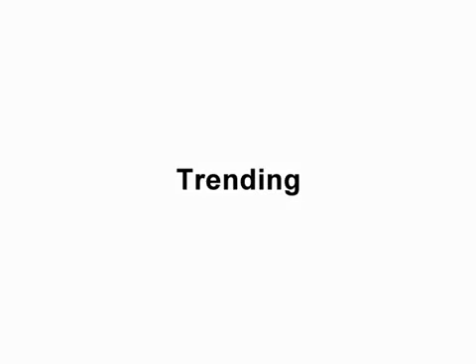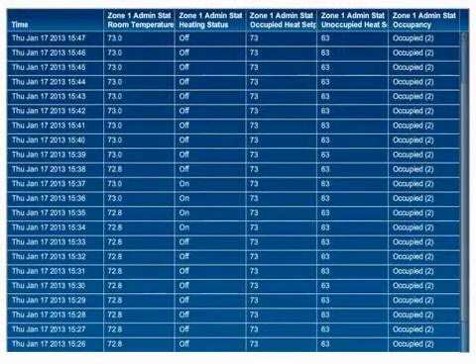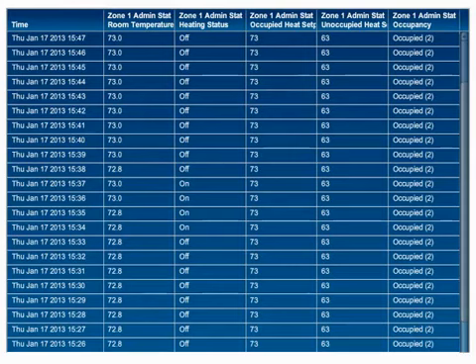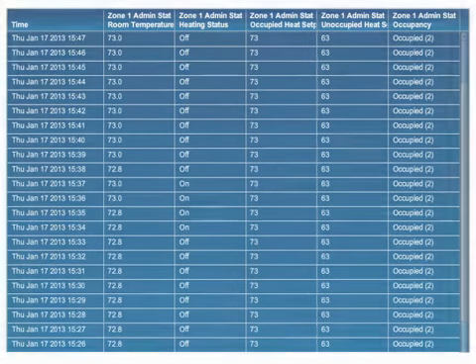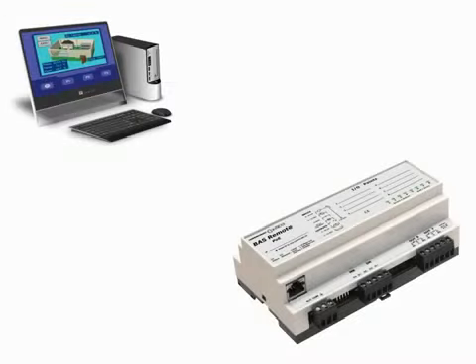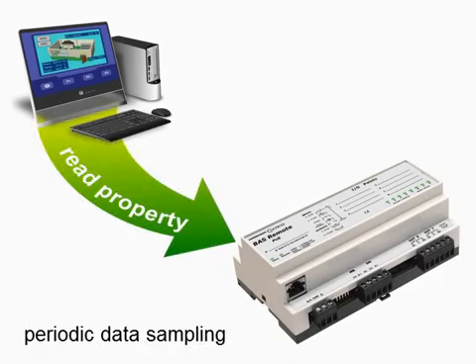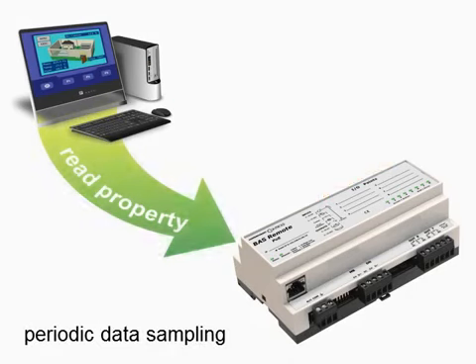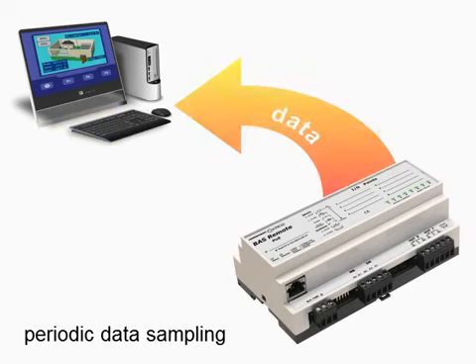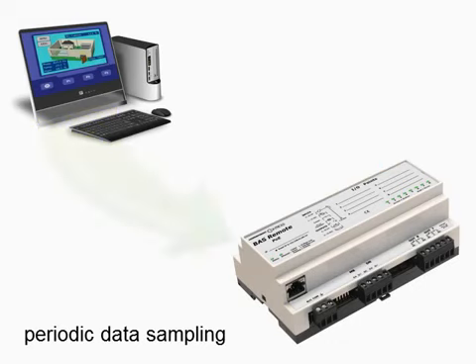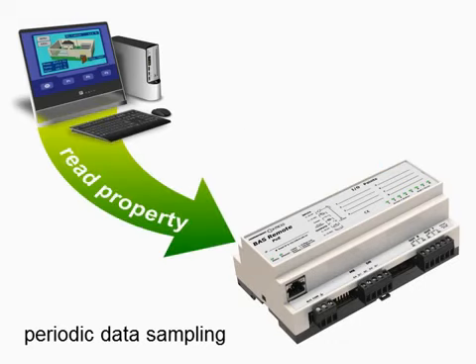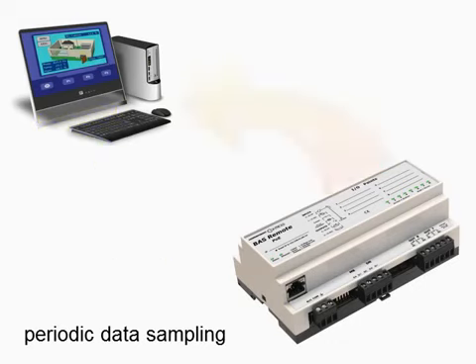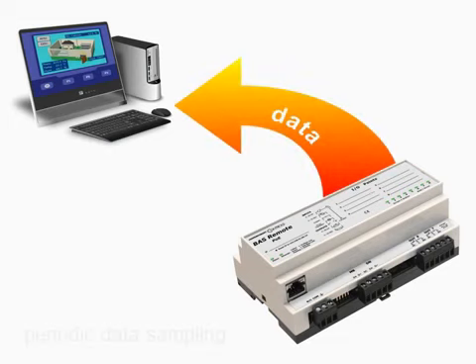The fourth area is trending, where data is sampled over time and stored for future review. Trending allows BACnet devices to enable trend collection and request trend data from other BACnet devices. One possibility is to simply use read property, or COV, to periodically sample data in devices from a centralized client location, but this could prove inefficient.